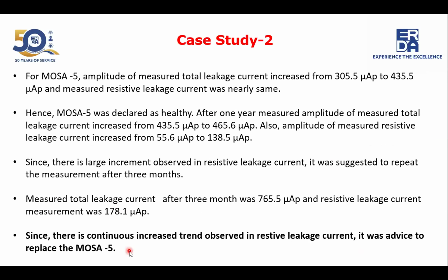For the MOSA 5, we also observe an increasing trend. The measured total leakage current after 3 months was 765 microampere, and the resistive leakage current was 178. Since there is a continuous increasing trend in the resistive leakage current, it was advised to replace the MOSA 5.